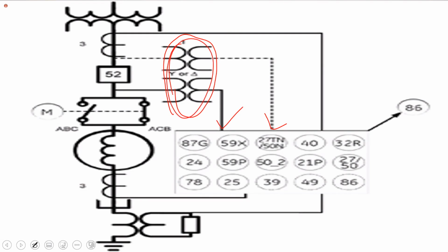Remember your current transformer, your CT, how is it connected in with the system? In series. These are not in series, these are in parallel. So those are voltage transformers. Okay? And what you have here, this and that, those would be your CTs. Those would be current transformers.